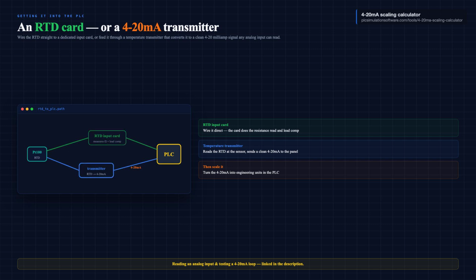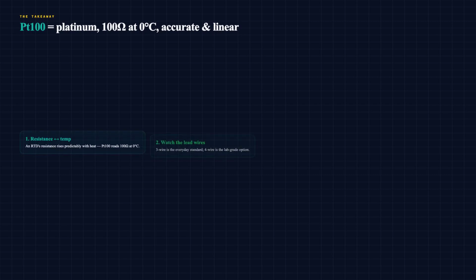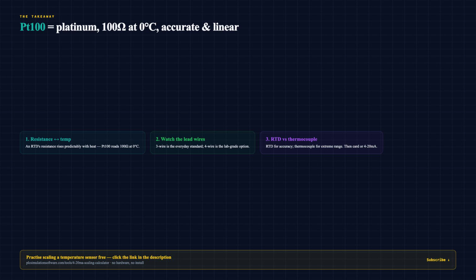An RTD is a resistance temperature detector. Its resistance rises predictably with heat. A Pt100 is the common one: platinum, 100 ohms at 0 degrees, very linear and very accurate. Watch the lead wires. 3-wire is the everyday standard. 4-wire is the lab-grade option. Pick an RTD for accuracy and stability, a thermocouple for extreme range, and it reaches the PLC through an RTD card or a 4 to 20 milliamp transmitter. Get that, and every temperature loop on the plant makes sense.